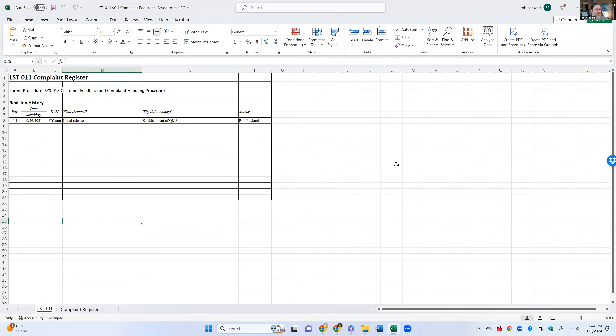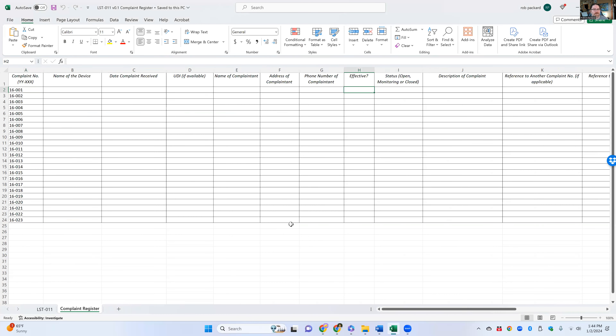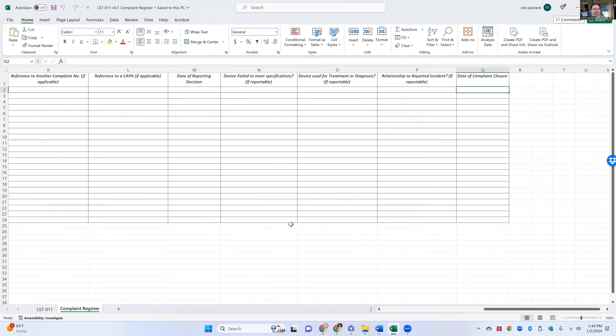Now let me show you the inside of the actual procedures. First, we're going to show you the log — this is LST-011. This gives you the revision history page. It's an Excel spreadsheet. It's a fairly wide table because it covers all of the extra requirements that are minimum requirements in a complaint record for anything requiring medical device reporting. They ask you: does the device fail to meet specifications? Was it used for treatment or diagnosis? What relationship does it have to the reported incident? And then complaint closure is a metric at the end.